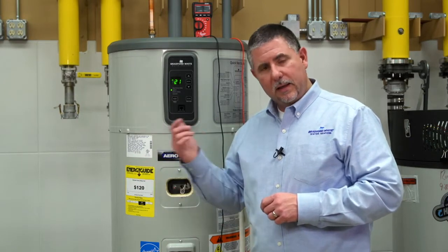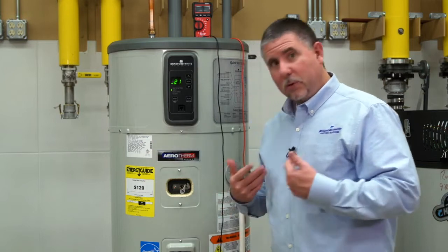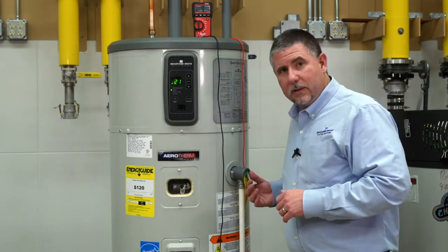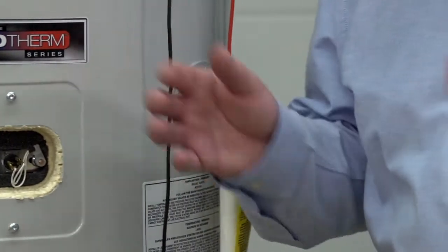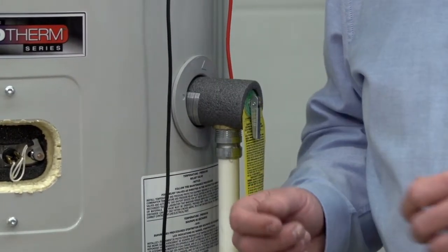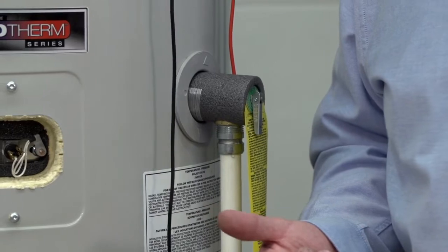So with that F11 code, we've got a couple of things we've got to do. One, verify water. Do that, your best practice. Personally, I'm going to open up the drain valve, making sure it's going to be caught into a bucket or something like that. Make sure you got water at the drain valve. You could also go to the T&P valve. There's a lot of mystery, should you trip that or not. But again, that's another way to verify you have water in the tank. Lastly, you could probably go to a faucet. Open up the hot water faucet. Again, the water may not be warm, but you should get a steady stream of water out of that hot tap.